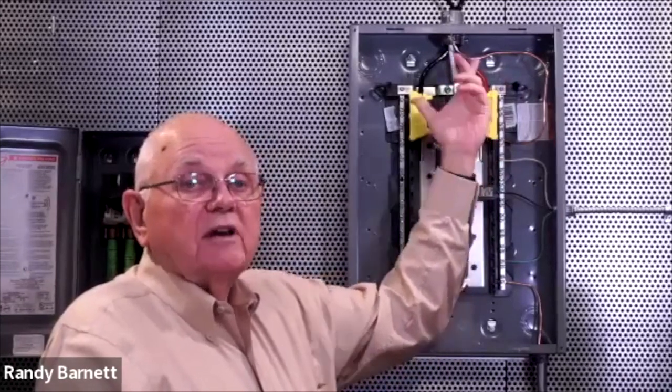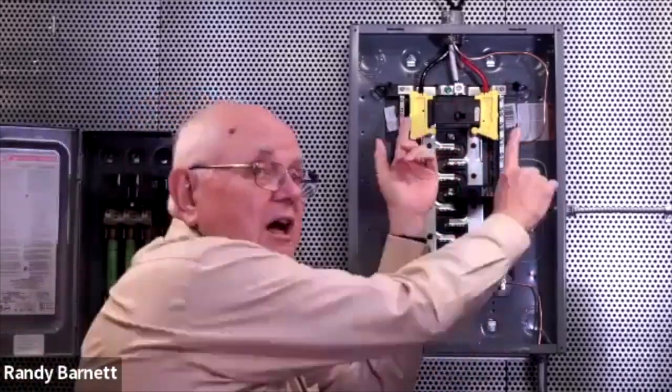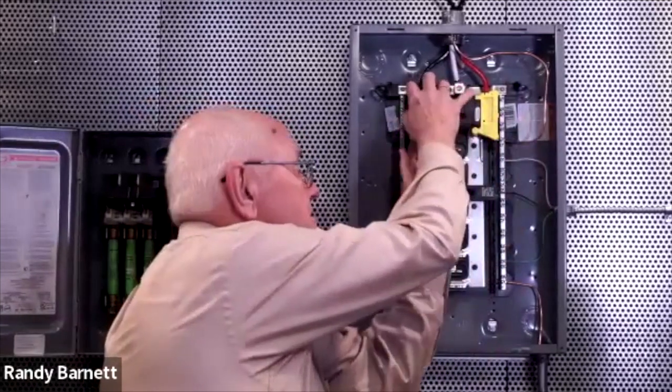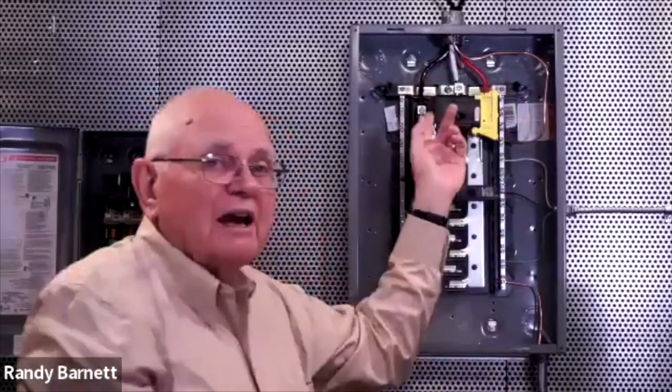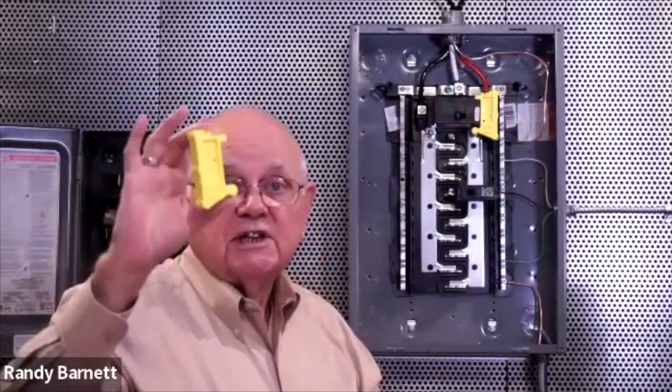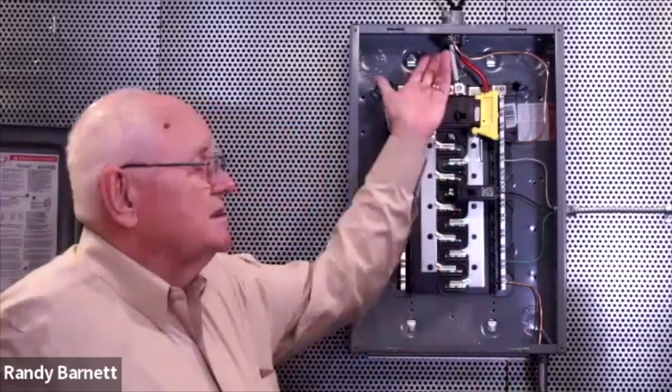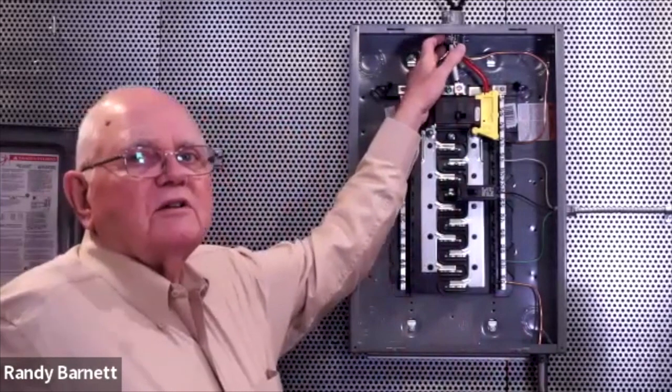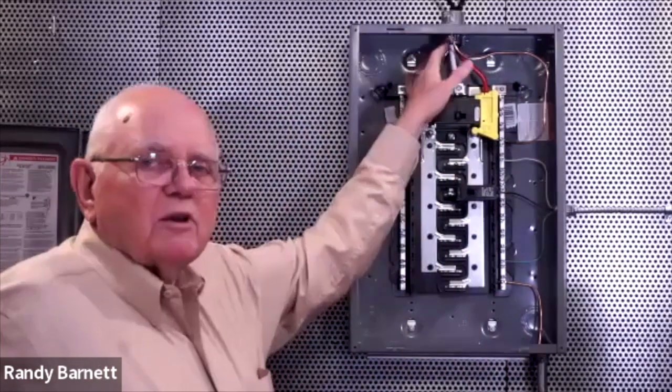And this is our very first disconnect. So we have to always consider, even though we turn the disconnect off, those 2 terminals behind those barriers are energized. And so we need some protection from inadvertent contact. But we're going to find similar rules for feeders as well. What if these conductors are not the service coming in from up here at the top? What if these are coming from a transformer that we own in the building? Then, of course, this is a separately derived system.